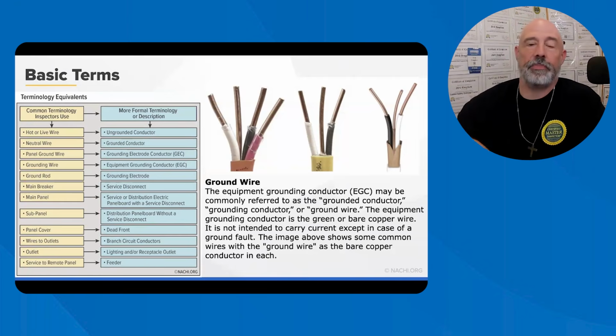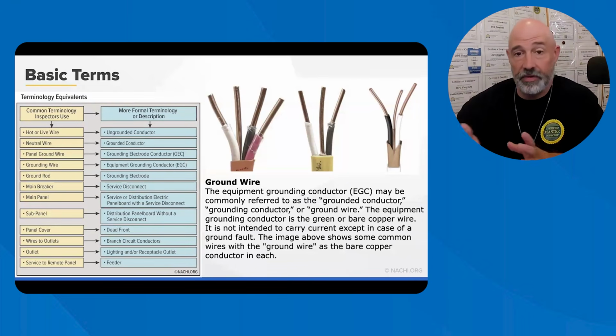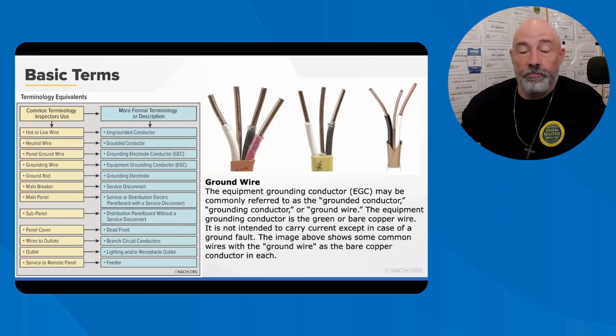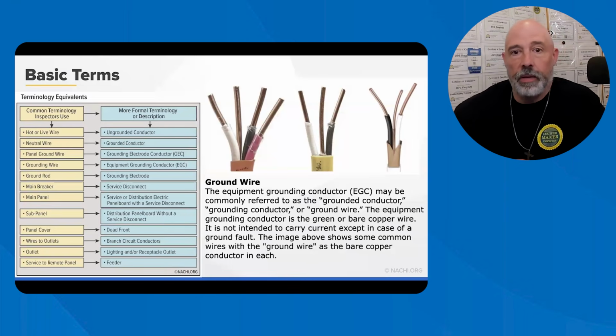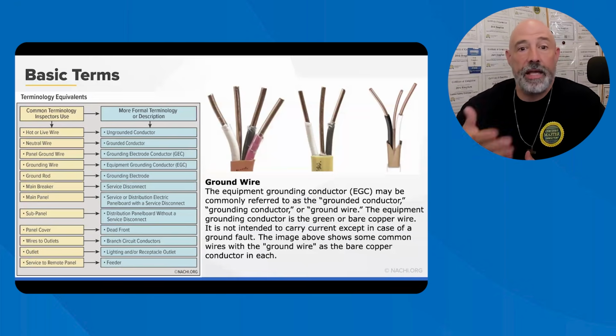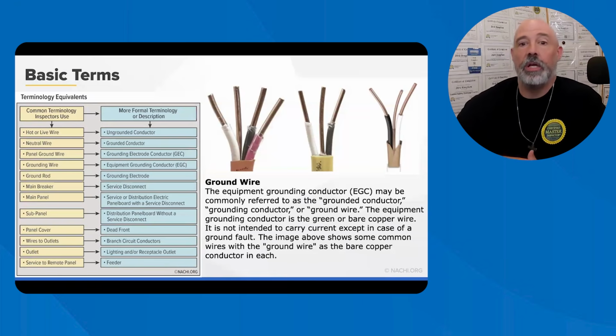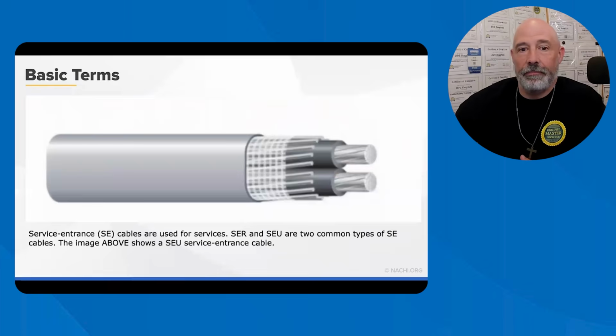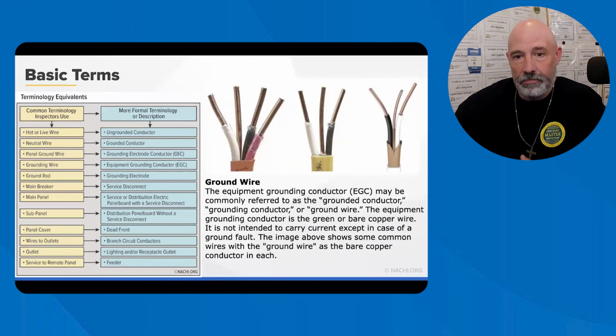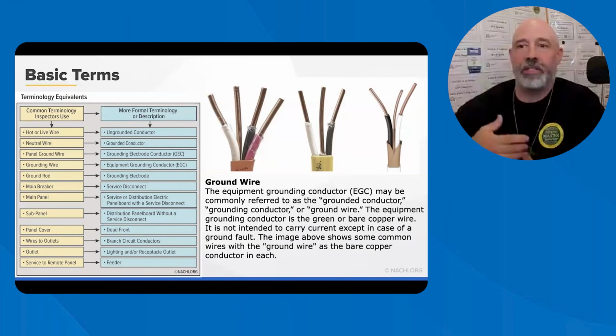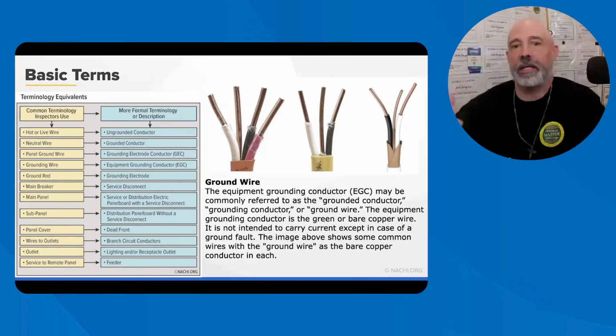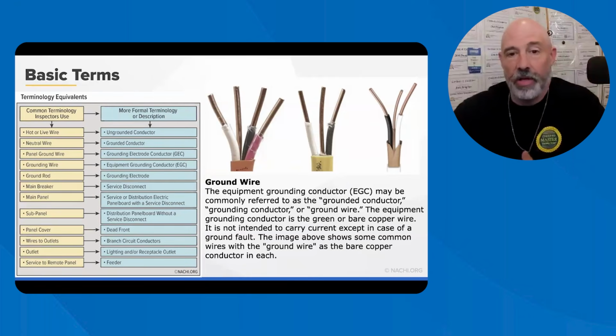Common electrical terms are ampacity, which is the maximum current a conductor can safely carry, through any type of conductor wire or through that circuit breaker. Appliance, now that's an equipment. Of course, you all know what appliances are, like a refrigerator, air conditioner, clothes washer, dryer, things like that. An AFCI, which is an arc fault circuit interrupter. You got the AWG, which is the American Wire Gauge, and that's the standard sizing system for conductors. The larger number indicates smaller conductors. So that's kind of how that works.